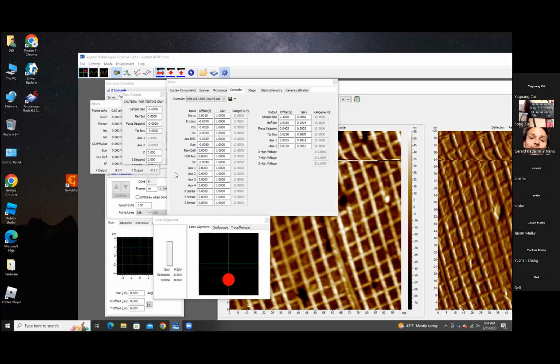Last but not least, one of the things that you may or may not notice is all of the gains on your inputs are still set to 1. We didn't adjust any of the gains. That is your default calibration from the factory. The factory never adjusts these gains. If you are working with something like electrochemistry, it's important for you to understand how to adjust your gains as well, but you have to be able to do that on your own.